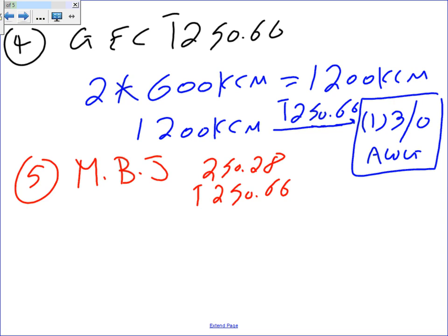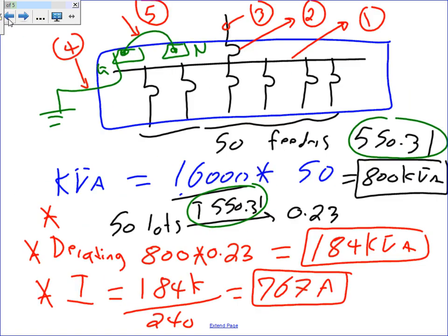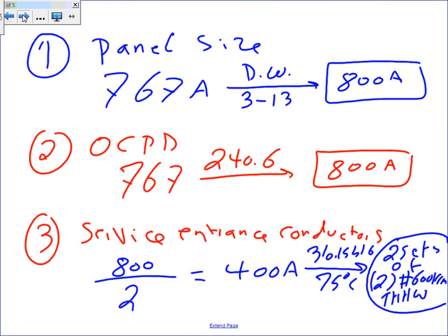You and William today. Everybody knows what the grounding conductor is, guys, the one that's going directly to the steel of the building or the ground rod, or with exception, ground rod, there's an exception. If it's going directly to the ground rod, you don't have to go higher than number 6. But we don't know if it's going directly to the ground rod. It could be going to a bar inside the building, and from the building, it goes to the ground rod. So that's why we start with this sizing. All right, so we got 4.